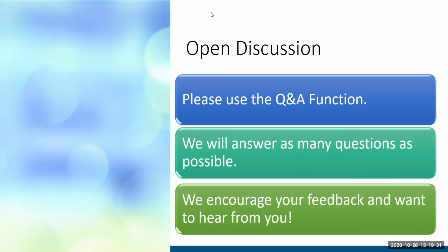The next question, when a patient is placed on comfort care and eventually died and did not remove or explant the device, do we need to complete the explant form or just the death form? You would actually complete the explant form, and you would choose that since the device was left in. I'm assuming it was turned off. If it was turned off and left in, that's considered that the device is decommissioned. So you would choose that option on the explant form. And the reason would be withdrawal of care.